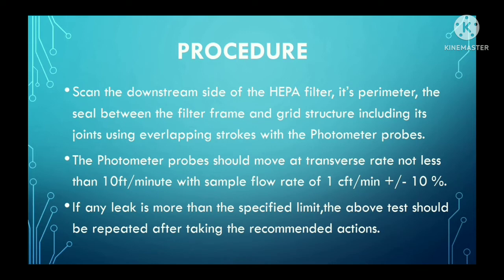Step 4: Scan the downstream side of the HEPA filter, the seal between the filter frame and grid structure including its joints, using overlapping strokes with the photometer probe. Step 5: The photometer probe should move at a traverse rate of not more than 10 feet per minute with a sample flow rate of 1 cubic feet per minute plus or minus 10 percent.